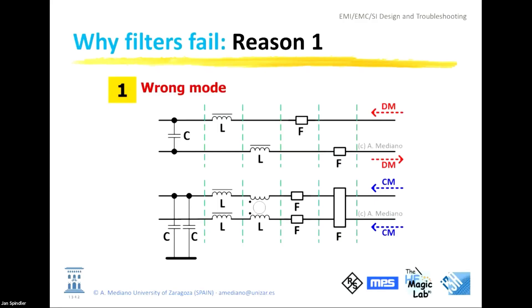The first thing to consider is whether you are filtering in the correct mode. Are you filtering differential mode or common mode? For differential mode, you might introduce a capacitor between the lines. Another option is to introduce an inductor — the core could be iron powder or ferrite, depending on the frequency range. This means you are working in micro-Henrys or nano-Henrys. If you introduce the inductor in the ground line, some people don't like it because this creates impedance and can cause ground bouncing.